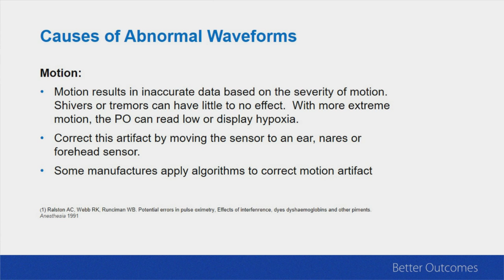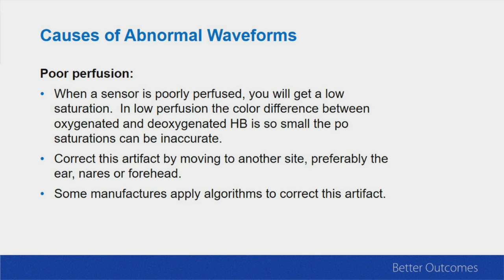So with poor perfusion, you end up with a situation where we just don't have a good exchange of blood coming to that site. You're going to end up with a low saturation. In low perfusion, the color difference between the oxygenated and the deoxygenated hemoglobin is so small, the pulse ox saturations can and could be inaccurate. So again, you correct this artifact by moving to another site. Again, preferably you're going to move to the ear, the nares, or the forehead. Now, poor perfusion is another area where manufacturers are going to apply an algorithm to correct for that artifact.